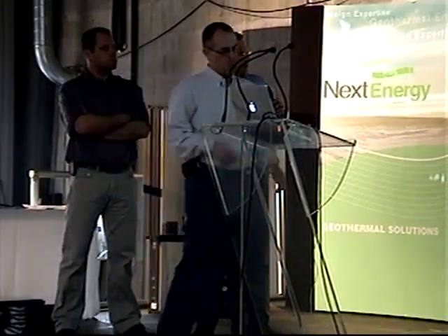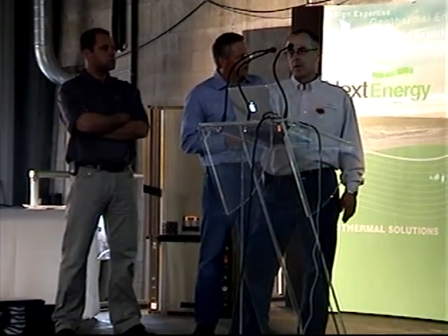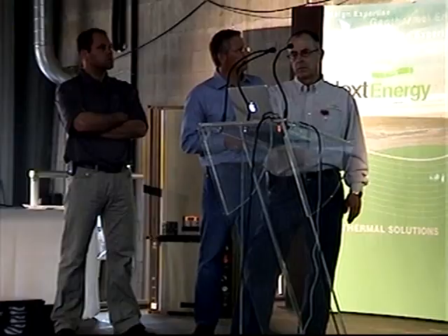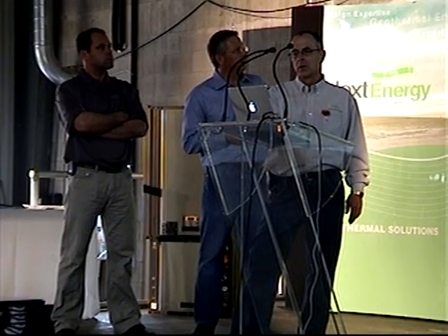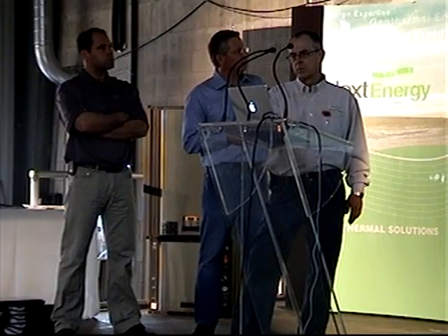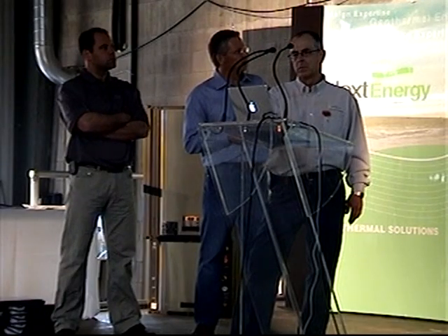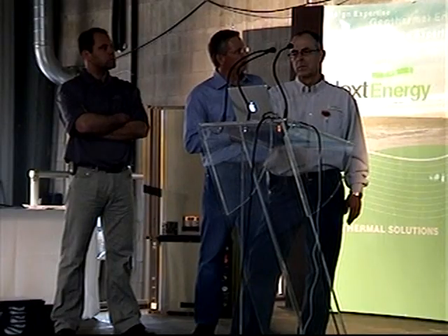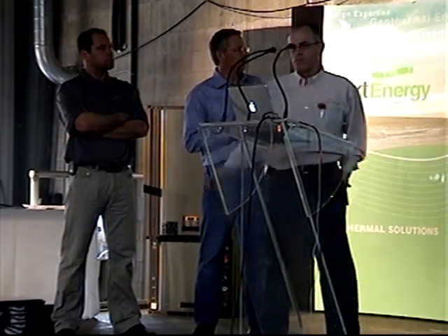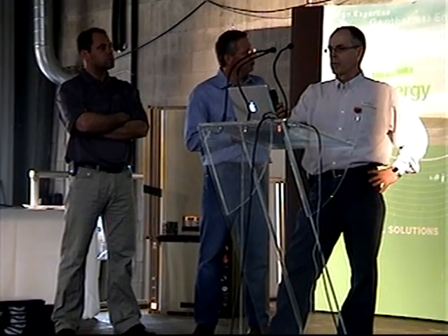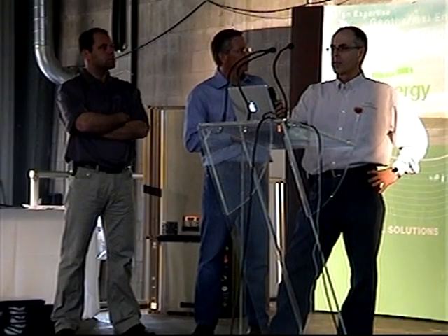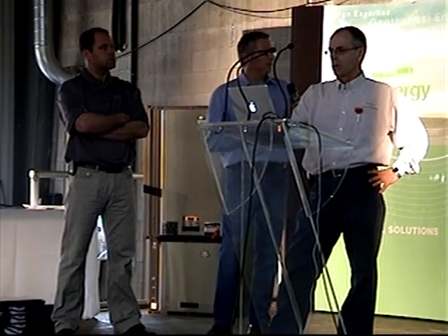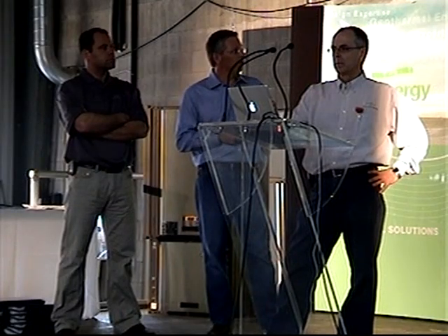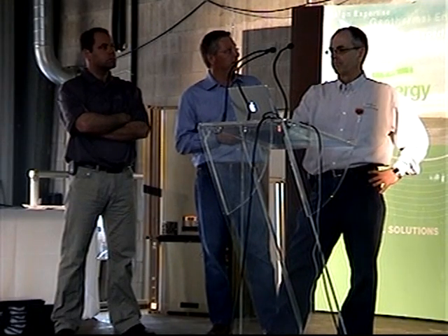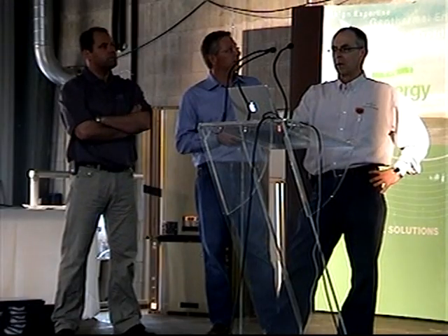Your LED should be shown on here, but it's on the board somewhere here. Yeah, well, that's the DXM. Yeah, there's the LED. There's the test pins. There's the dip switches, and there used to be 3 jumpers you could clip. We now just have 5 dip switches. And that's really for some commercial features we stuck on here. You really don't need too much of that for residential. There's your jumpers for FP1 and 2. You really would never use FP2 unless it'd be a real strange thing you would ever clip that for. And that's pretty well it on that.